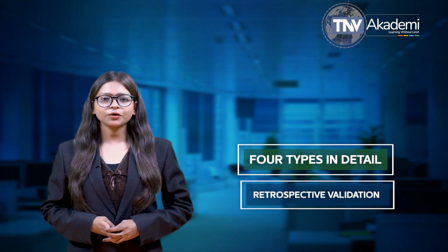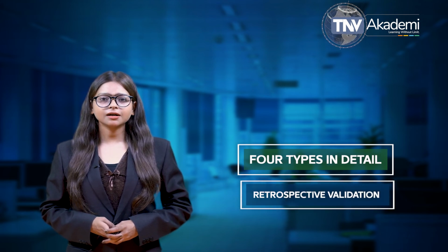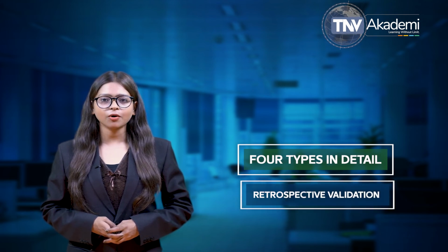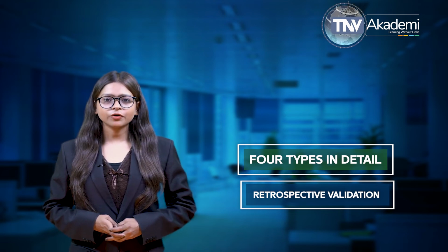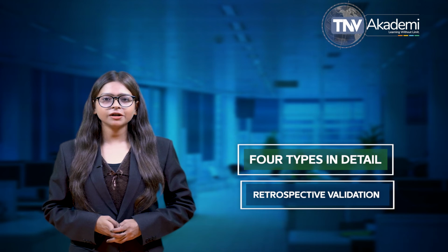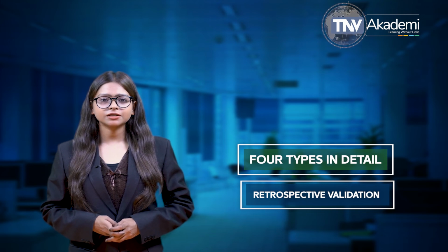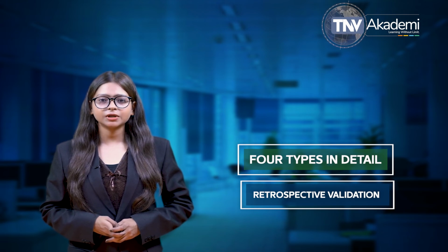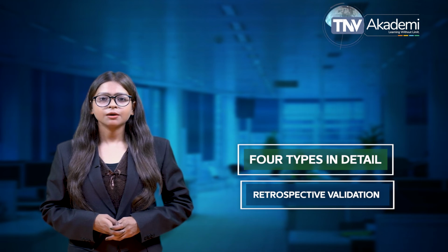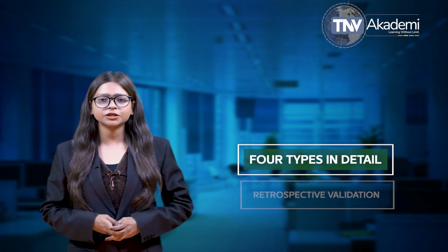Type 2. Retrospective validation. It is conducted only when the manufacturing process has not formally undergone a documented validation. Retrospective validation is normally fulfilled with the use of historical data and trends analysis to provide evidence that the process is at a state that it is intended to be in. In most cases, it is no longer an acceptable approach to process validation because any product should have already been validated before its commercial distribution.